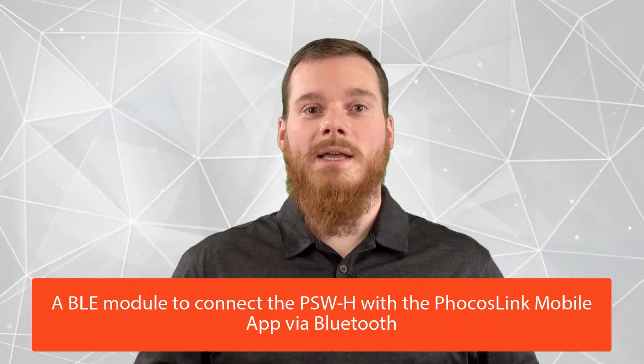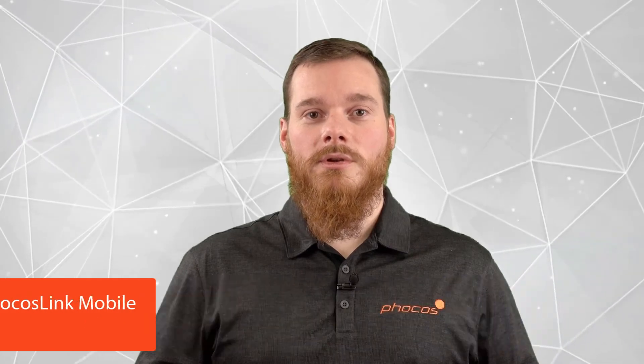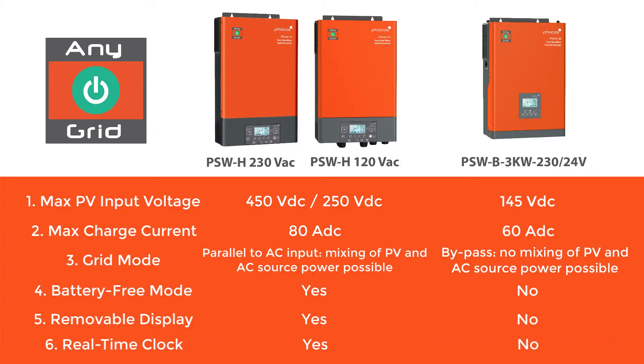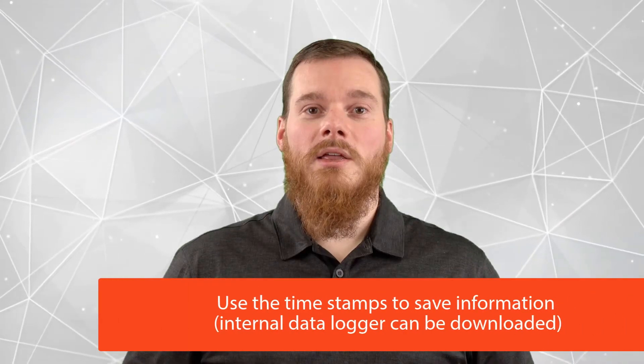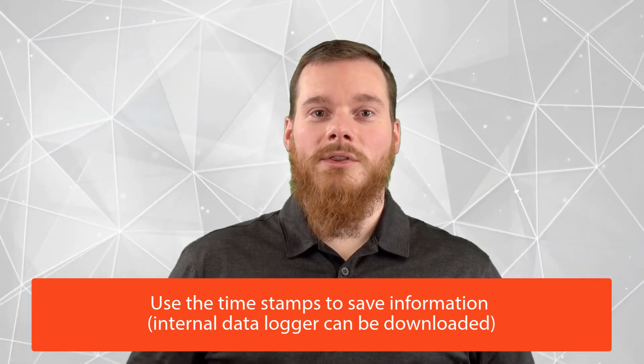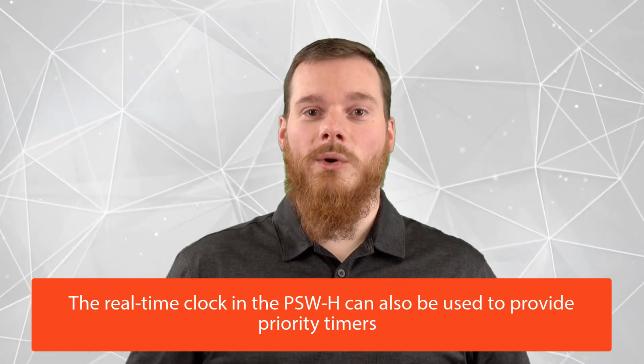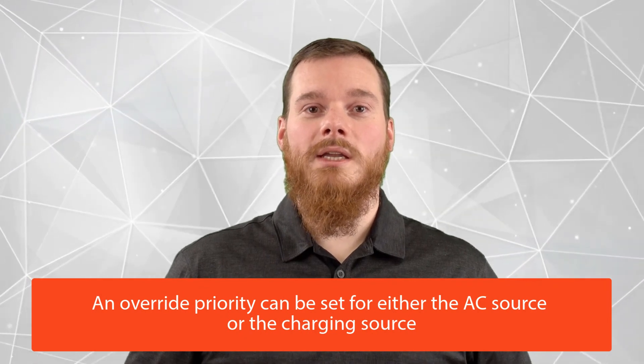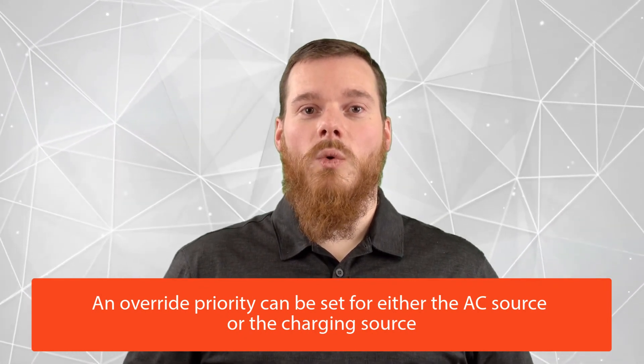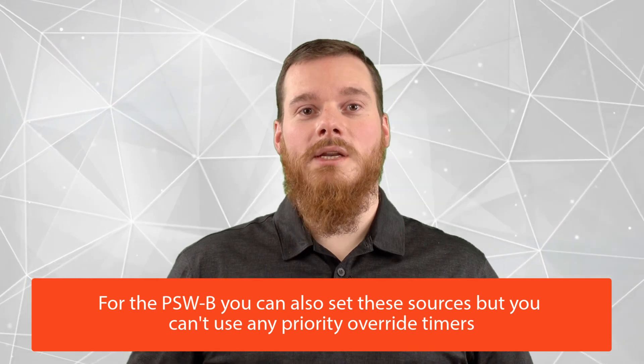Furthermore, the removable display has a BLE module, which means you can connect the PSWH with the PhocosLink mobile app via Bluetooth. The PSWH also has an integrated clock, allowing it to use timestamps to save information. The internal data logger can be downloaded via a USB OTG device to debug the unit or to look deeper into the energy flows of your system and the state of various components. This real-time clock can also be used to provide priority timers — you can set an override priority for either the AC source or the charging source. For the PSW-B, you can also set these sources, however you cannot use any priority override timers.